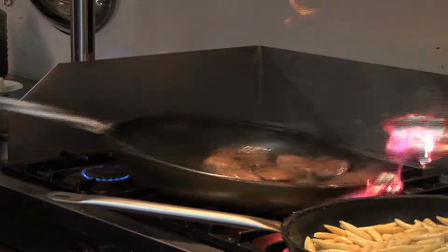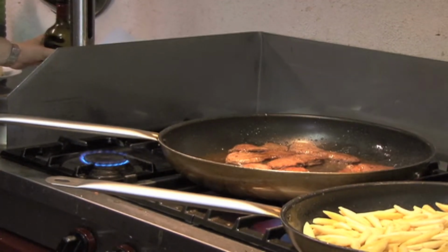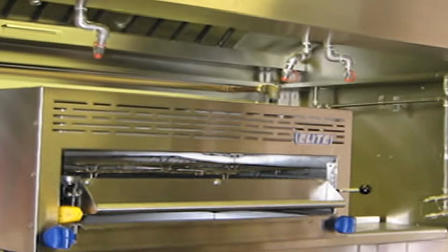As Leo said previously, we have grease-laden vapors in the air and we have an ignition source. So we want to make sure that your commercial kitchen exhaust is clean. The way your kitchen equipment is laid out and positioned is crucial. The ductwork has to be accessible. Besides every turn needing a clean out, the horizontal duct also needs clean outs every 10 to 15 feet, or more often if needed. Fire suppression is crucial to be in place.